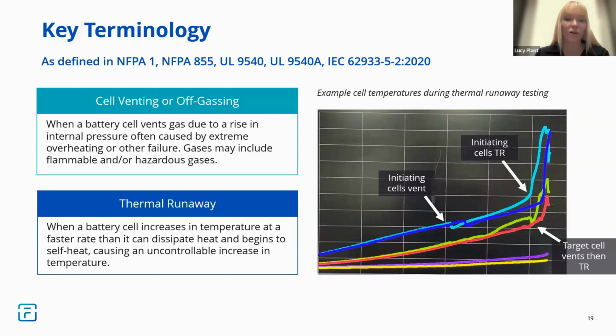There is no amount of gas suppression, gases or foams that can stop that event. It is a thermal event. It is a chemical event. And once this thermal runaway starts, the only option then is to let the system burn. If you try and put water on it, if you try and put any sort of gas or foam on that, all you're going to do is delay and extend the event. That's why Fluence's approach to fire safety and to fire events within these systems is always a let-it-burn philosophy.